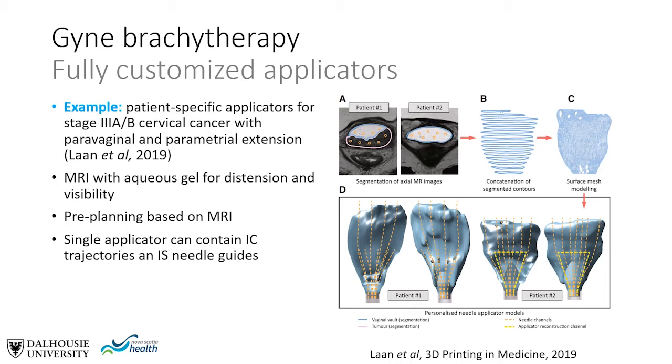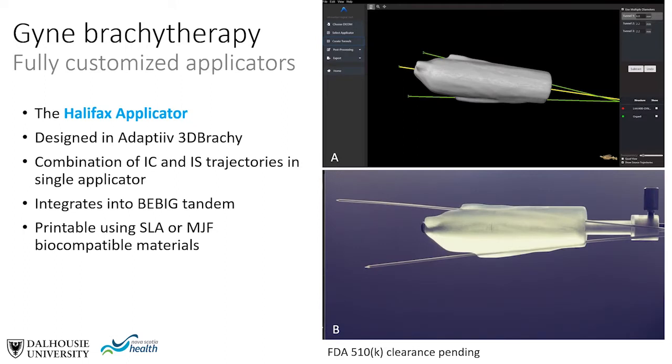This approach was applied to patients with customized definition of both intracavitary source trajectories and interstitial needle guides. Here's a similar example produced with commercial software for treatment of vaginal cancer including extensive paravaginal disease. The design application allows input from and export back to the treatment planning system, and exports 3D printing data for production of the applicator through multi-jet fusion or SLA printing using biocompatible materials, compatible with standard hardware such as a BEBIG tandem.